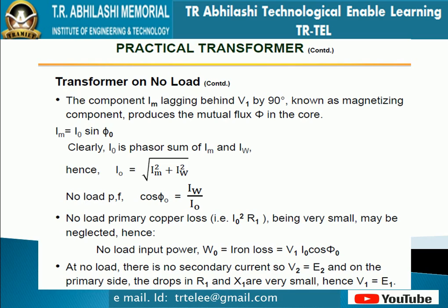Since we have a very small value of current, the losses are very less, so it can be neglected. In no load transformer, we neglect the copper loss and consider only the iron loss. So no load input power, W naught, is equal to iron loss, equal to V1 I naught cos of phi naught.